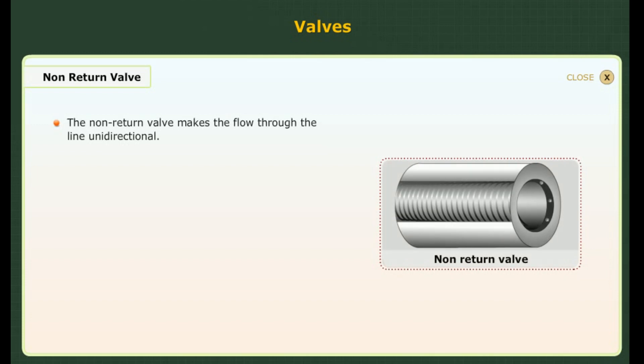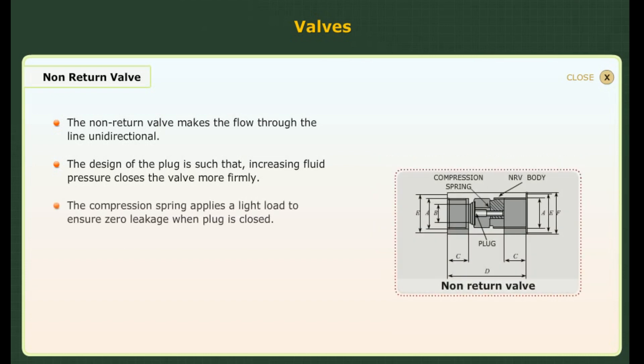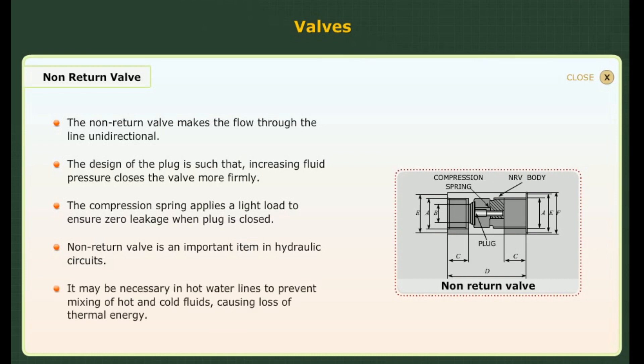Non-return valve. The non-return valve makes the flow through the line unidirectional. The design of the plug is such that increasing fluid pressure closes the valve more firmly. The compression spring applies a light load to ensure zero leakage when the plug is closed. Non-return valve is an important item in hydraulic circuits. It may be necessary in hot water lines to prevent mixing of hot and cold fluids, causing loss of thermal energy.